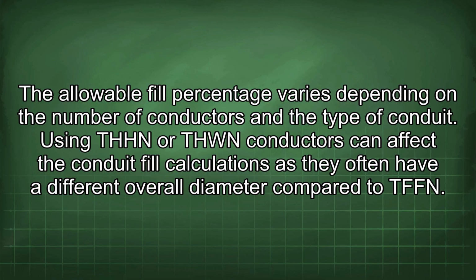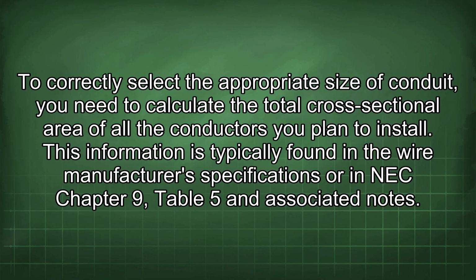Using THHN or THWN conductors can affect the conduit fill calculations, as they often have a different overall diameter compared to TFFN. To correctly select the appropriate size of conduit, you need to calculate the total cross-sectional area of all the conductors you plan to install. This information is typically found in the wire manufacturer's specifications or in NEC Chapter 9, Table 5 and associated notes.